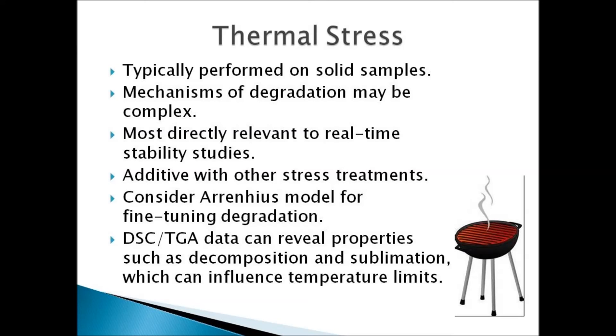Never fail to take advantage of DSC or thermogravimetric analysis data that can reveal properties such as melting points, decomposition, and sublimation, which can influence your temperature limits. Be careful that you know sublimation is happening, because when you degrade a sample, you want to account for degradation product peaks. If you're subliming, your material is just going away and there's going to be a failure to get mass balance.